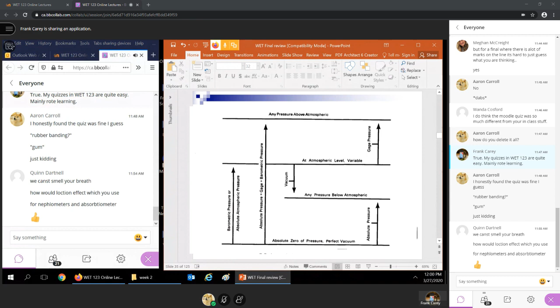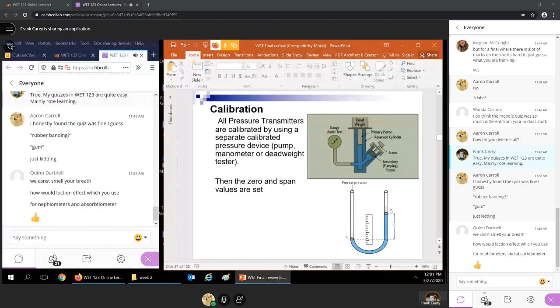So we use a hand pump, just an air hand pump. There's another method using a dead weight, so a weight just pushes down on a fluid inside here, either air or liquid, and gives an exact pressure. Or the most exact, the standard is generally a manometer with mercury inside. But because mercury is toxic, industry is getting away from that.